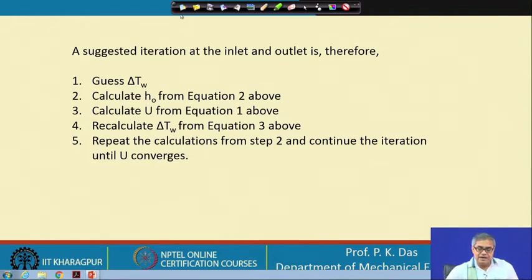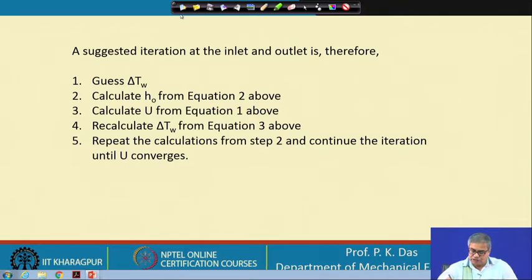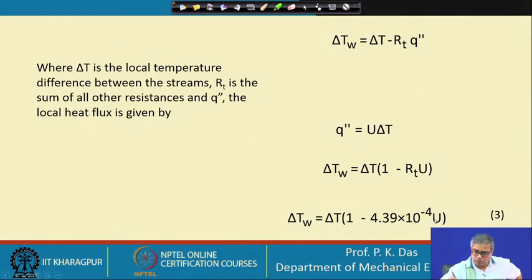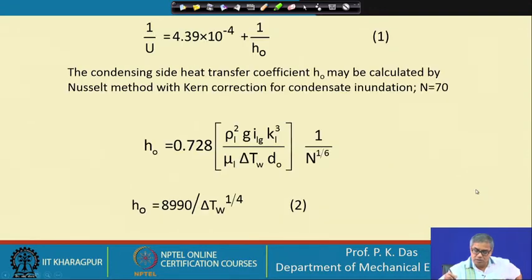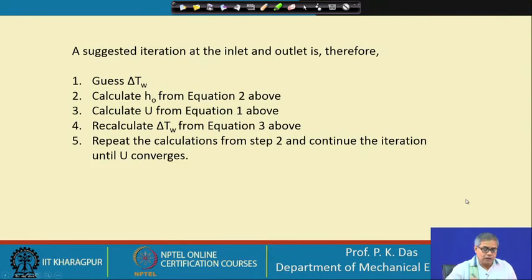The suggested iteration steps at the inlet and outlet are therefore: Step 1 — guess delta T_w. Step 2 — calculate H_o from equation 2. Step 3 — calculate U from equation 1. Step 4 — recalculate delta T_w from equation 3. Repeat from step 2 and continue the iteration until U converges.